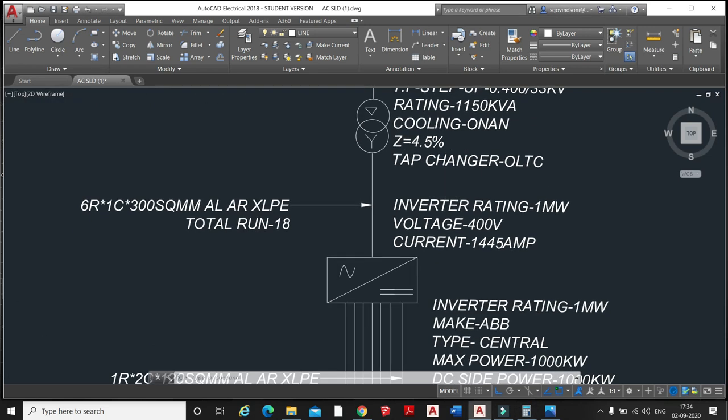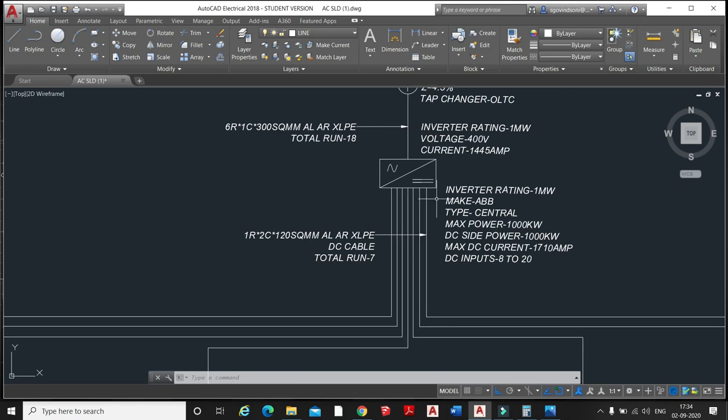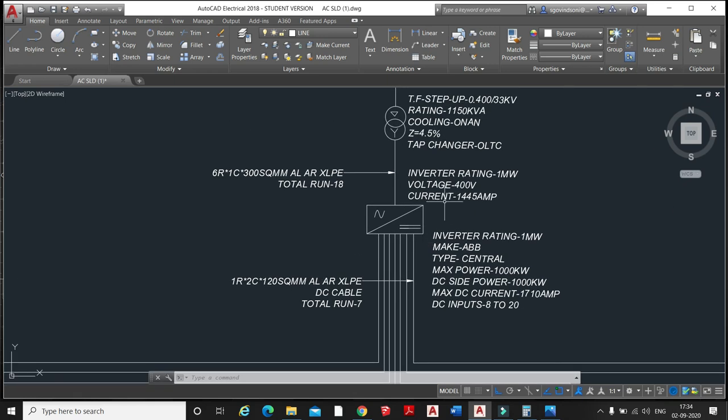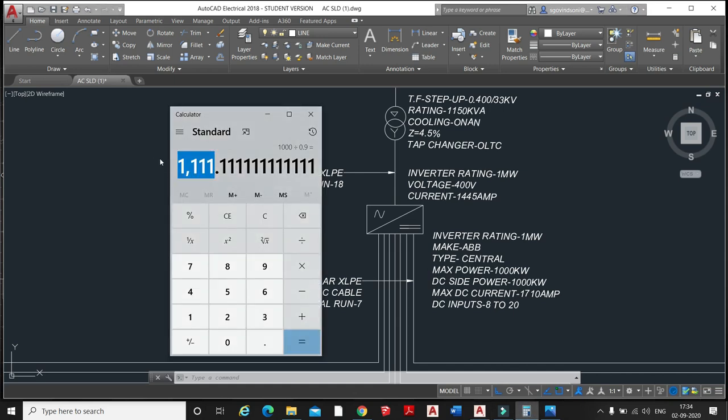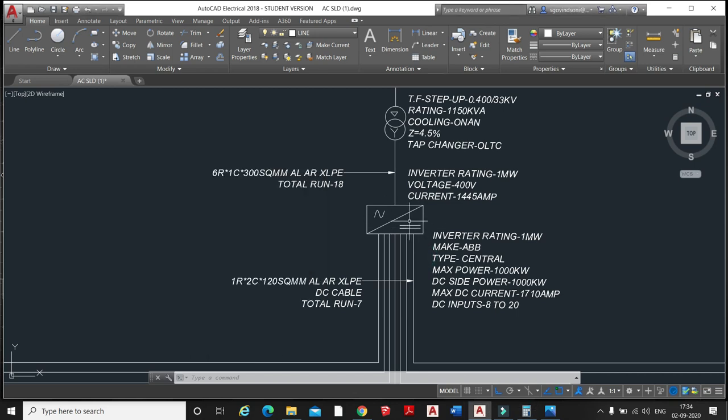Also, another method is, we know that the losses at the DC side are almost 15%, which include soiling losses, radiation losses, temperature losses, LID losses, and DC copper losses. So we have considered that 15% losses occur in the DC side. So we reduce the power, then we get 85%, into 0.85, so we will get 850 kilowatt DC output at the inverter end.